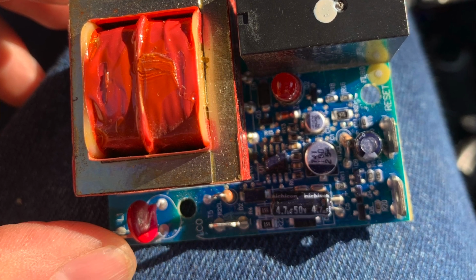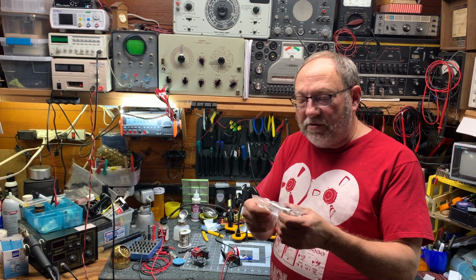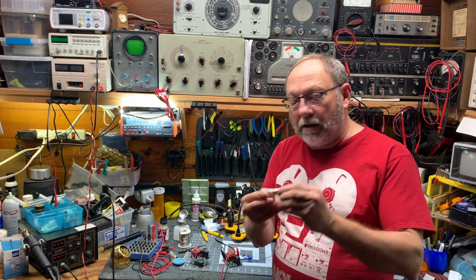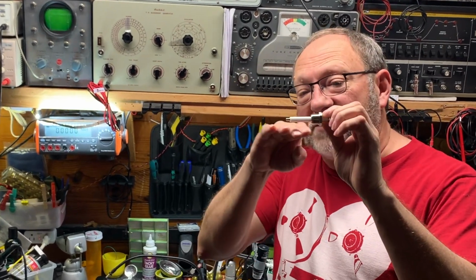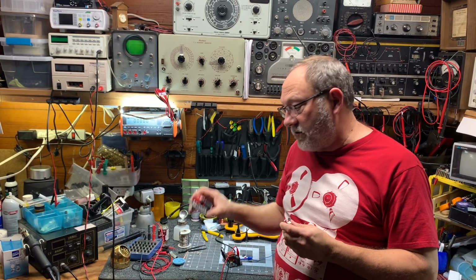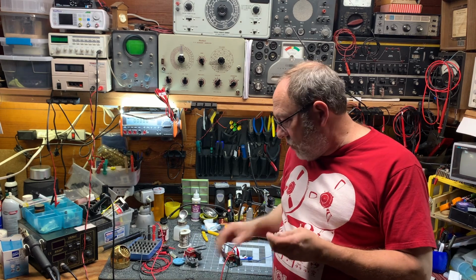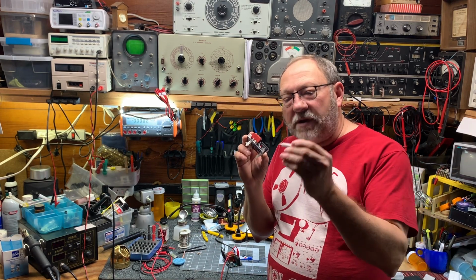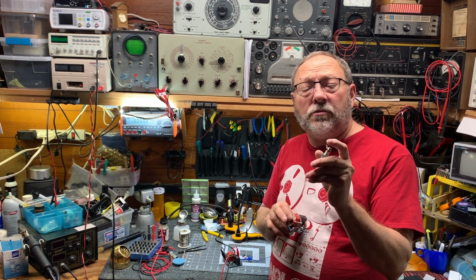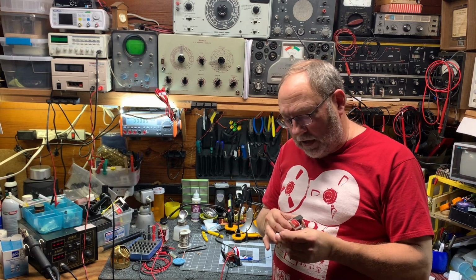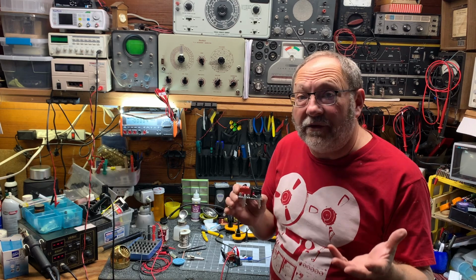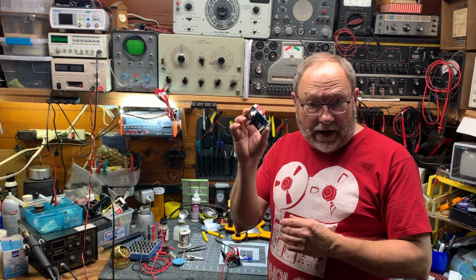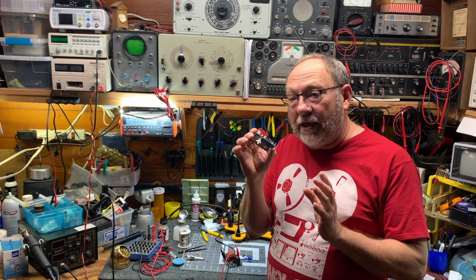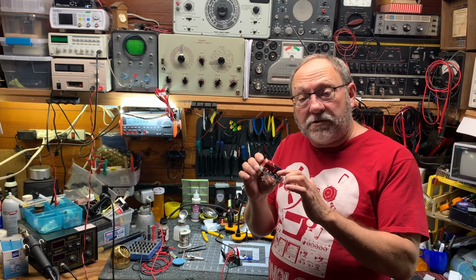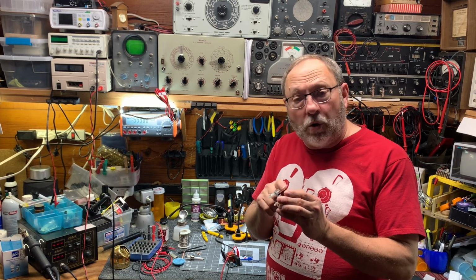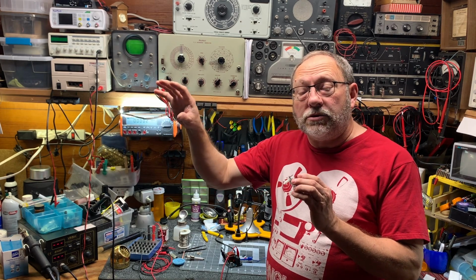Basically what it is, they use a probe inside at the top of the boiler that is probed right into the top of the vessel with a wire that comes over to the sensor, to the board. And the board is designed to detect the presence of water between the terminal of the probe and the ground of the vessel. And in this particular case, that's around 25 k ohms. And this module is designed to watch for about 25 k, and if that 25 k is missing, this module will sense that and open a relay and tell the boiler control to shut down.